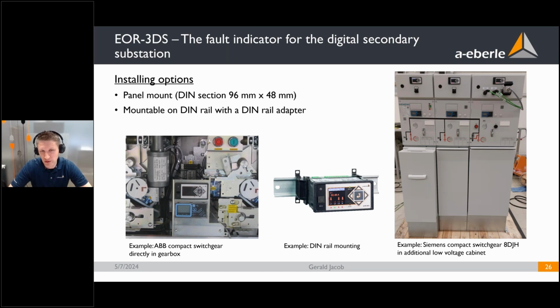Then you can also equip the device with DIN rail mounting adapters, as we saw for the EOR-1DS. And on the right side, we see there's also the possibility to order such a compact switchgear station with a low voltage compartment on the top, where you have separate doors per cable field and the transformer field. And yeah, this is the easiest way. You have a lot of space inside this low voltage compartment.